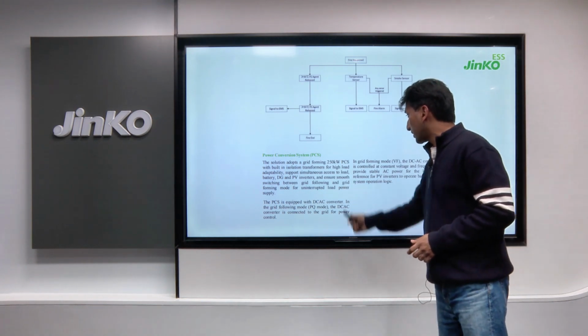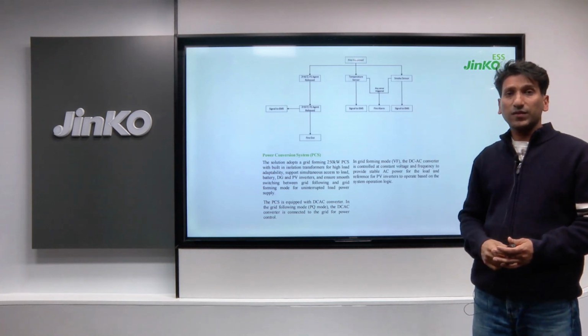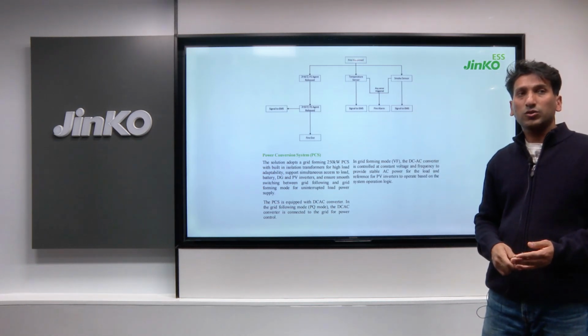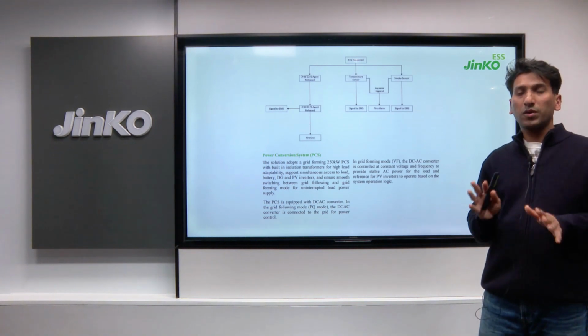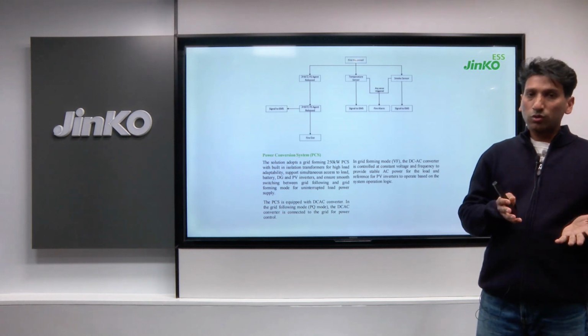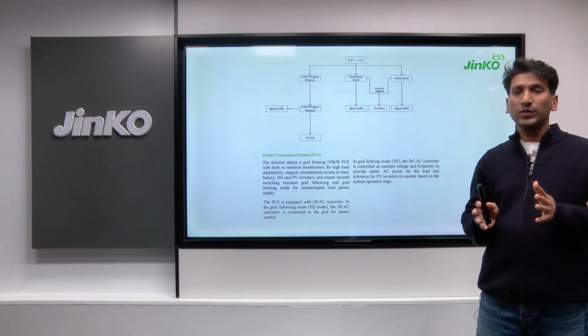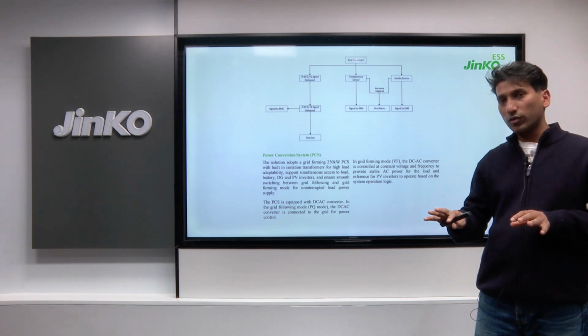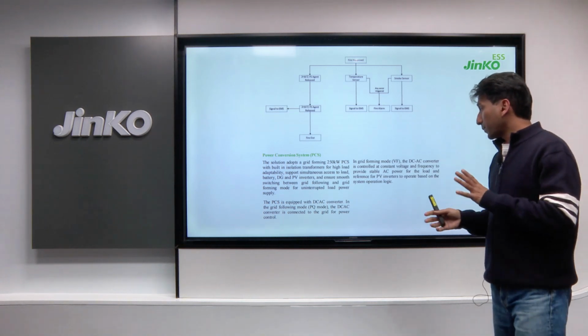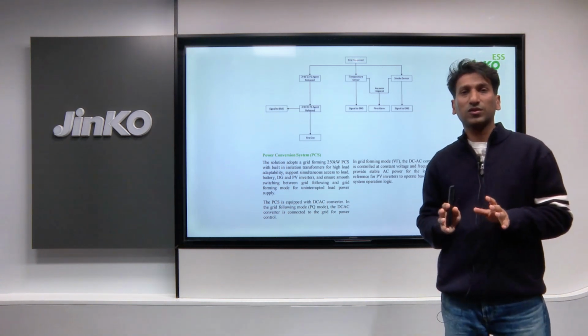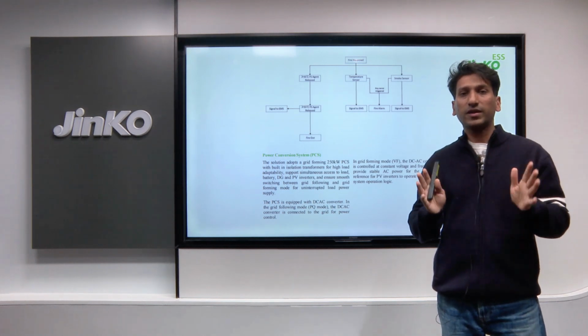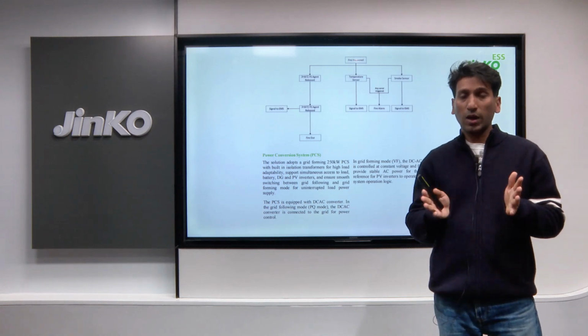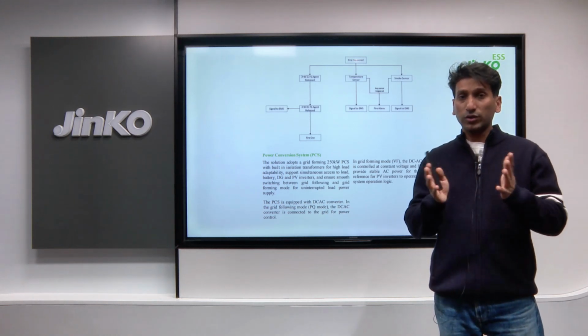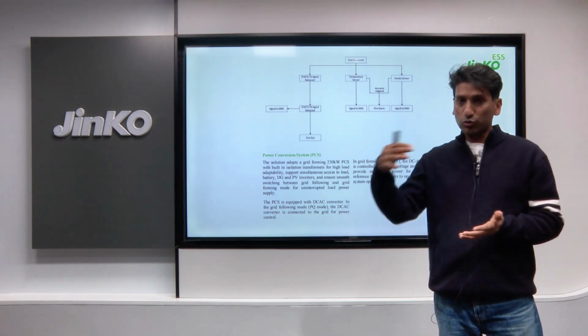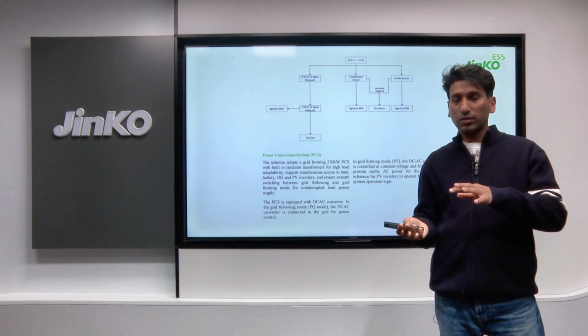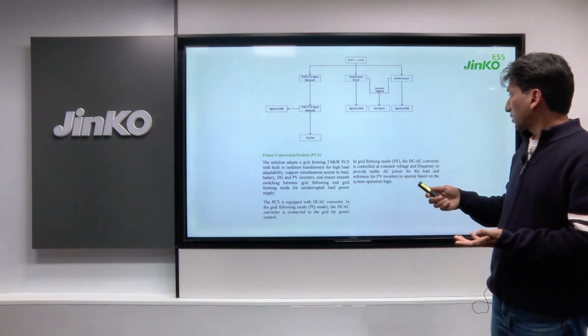We have also discussed the PCS that we have used. It is a 250 kilowatt PCS, and it can work in both on-grid and off-grid mode. It can also work with grid following ability and grid forming ability. It depends, because this site doesn't have any grid, so we have to use the grid forming ability of the PCS at some times of the day, so that we can use the PV power to charge the batteries. If there is no grid forming ability, it won't be able to charge the batteries.